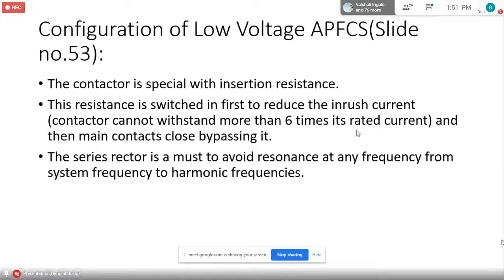because a contactor cannot withstand more than 6 times its rated current. So even though your capacitor can withstand a bit more, the contactor cannot. Then the main contacts close, bypassing it. So first the resistance comes into the circuit and reduces the current, then the main contacts close, and then the contactor gets the rated current. The series reactor is a must to avoid resonance at any frequency from system frequency to harmonic frequency.